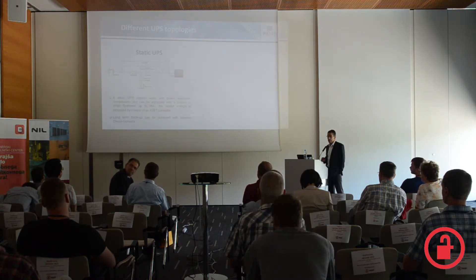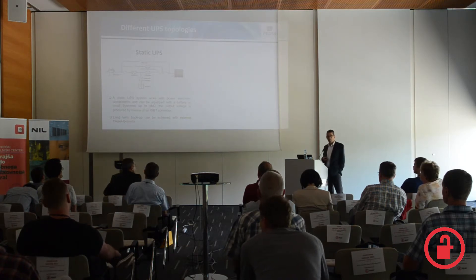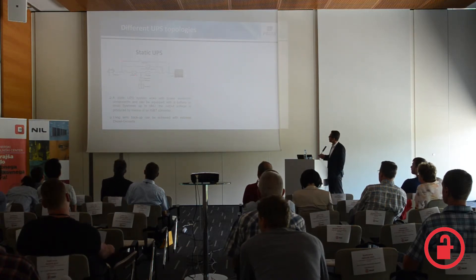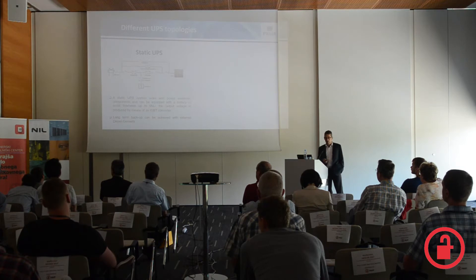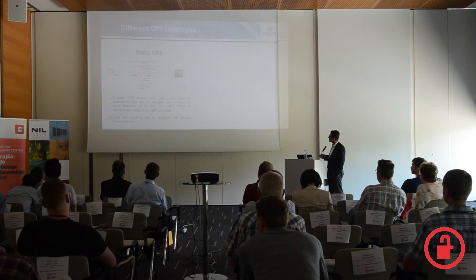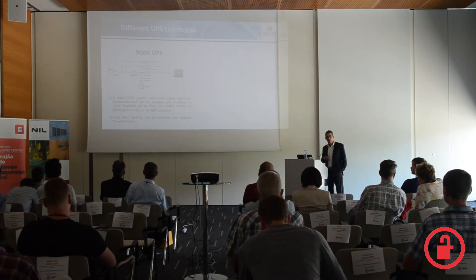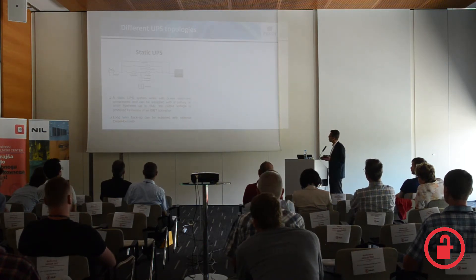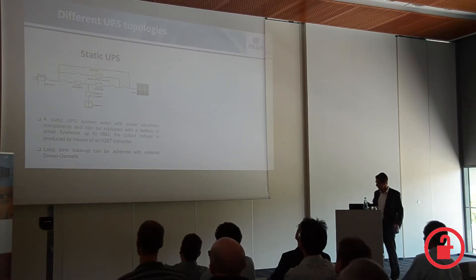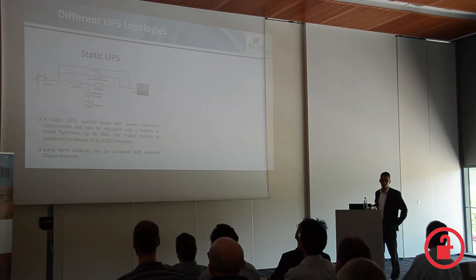First of all, we see an overview of the concept of a static UPS, which has main components of a rectifier, an inverter, and somewhere in the middle a battery connected. The normal way of operation is that the main AC is rectified to DC, where the battery works, and then AC is created again. This technology uses purely electronic components — control electronics and power electronics. Nowadays we find so-called IGBTs, very fast switching power transistors, inside to create the output voltage.